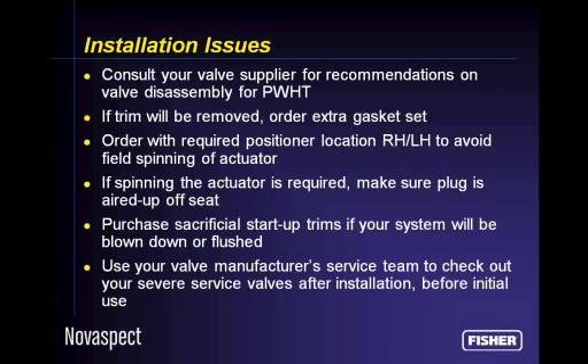All right. If you're going to blow down a piping system, it's new construction, and you've got to get rid of weld slag and dirt and lunch boxes that are in the pipe, put some sacrificial startup trims in there. We'll ship you a valve with startup trim in it. We'll keep the real trim at our service center. When you're done with your blowdown of your piping systems or your flushing, we'll come back and install the right trims, and we'll throw away the flushing trims.